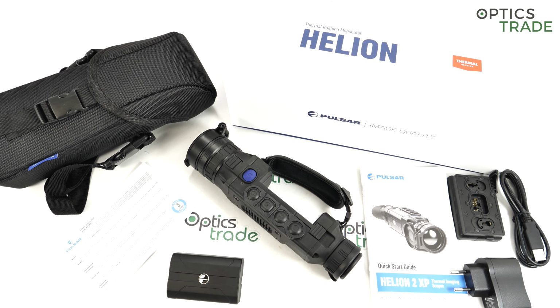The calibration on these devices is still manual, semi-automatic, and automatic. That means that every, I would say, 30 seconds or something like that, the image freezes for a short period of time so that the sensor gets recalibrated, so that all the pixels in the sensor get value 0 and you start from scratch again. That means if you're not doing the calibration often enough, the pixels get saturated and you're losing contrast. And I would say that the majority of people are just using these devices with an automatic mode for calibration.